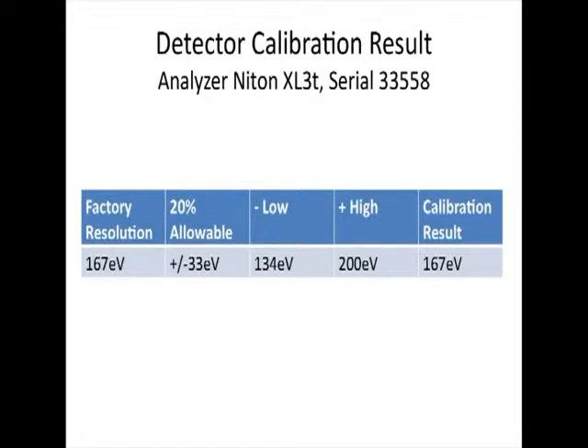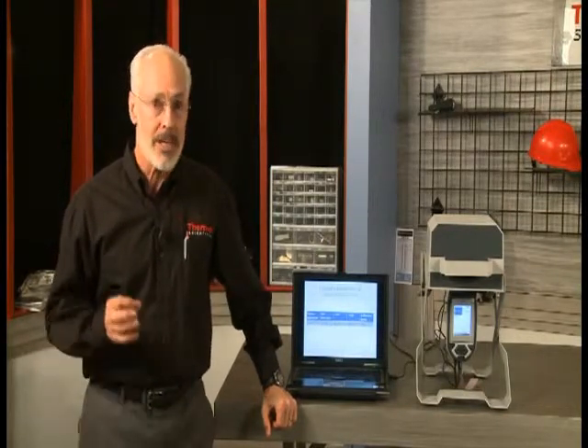A good diagnostic indicator of detector stability is the degree of change in the detector resolution value. We recommend monitoring this value at the conclusion of each detector calibration. If this value goes beyond the plus or minus 20% range of the resolution value when you first took delivery of the analyzer, please contact your nearest Thermo Scientific Niton Analyzer Service Center for assistance. You'll want to record the values of detector resolution from the calibration that you just performed. This will give you the initial value for future comparison.